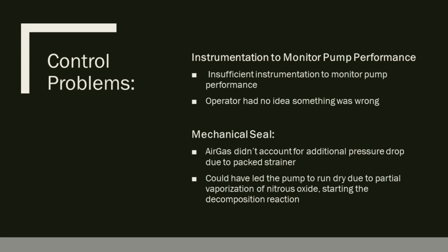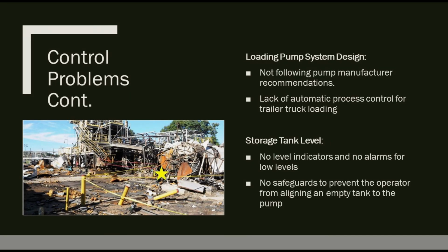This could have led the pump to run dry due to partial vaporization of nitrous oxide, starting the decomposition reaction. Packed strainers could have increased the pressure drop by a factor of 10. For the loading pump system design, the pump manufacturer recommendations were not followed. There was a lack of preventive maintenance programs for the nitrous oxide pumps since they were not cited as critical equipment.